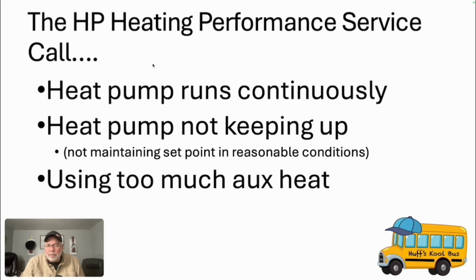Another complaint would be that it's using too much auxiliary heat, and the electric bill is too high, right? Some other things that also play into this is sometimes people will lock out their aux heat, whether it's electric heat or even if it's dual fuel, at a temperature that is just kind of arbitrary. They chose that temperature, and that may or may not be the right temperature to lock out that aux heat. They may be locking it out lower than what the system is capable of handling due to the actual load of the space.